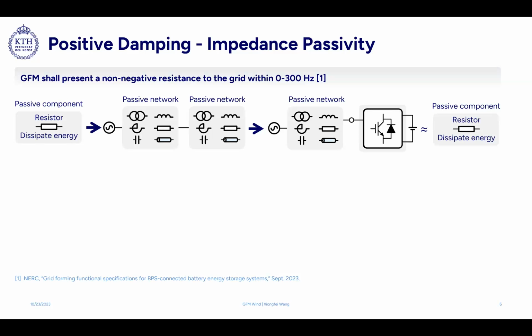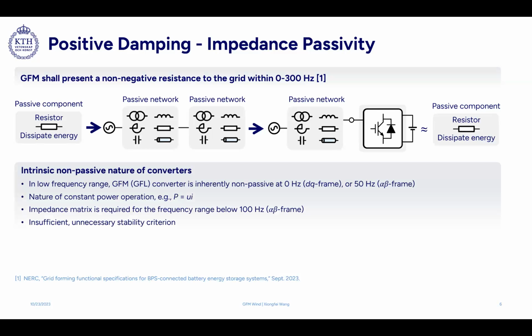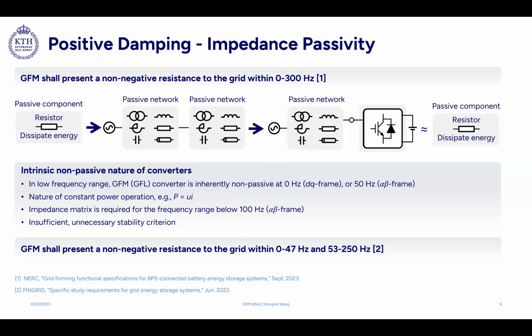oscillations or instabilities. But I would say this is too ideal. If we look at any type of constant power source or constant power load, we can never reach non-negative resistance around the fundamental frequency in the stationary frame, or 0 Hertz in the DQ synchronous reference frame. So that means we have to tolerate some negative resistance around the fundamental frequency. That's why in the latest requirement from Fingrid, the Finnish TSO, they mentioned all grid forming battery energy storage shall present a non-negative resistance within a certain frequency range excluding the fundamental frequency. Here they put 3 Hertz as the bandwidth around the fundamental frequency. To me, this is more reasonable.